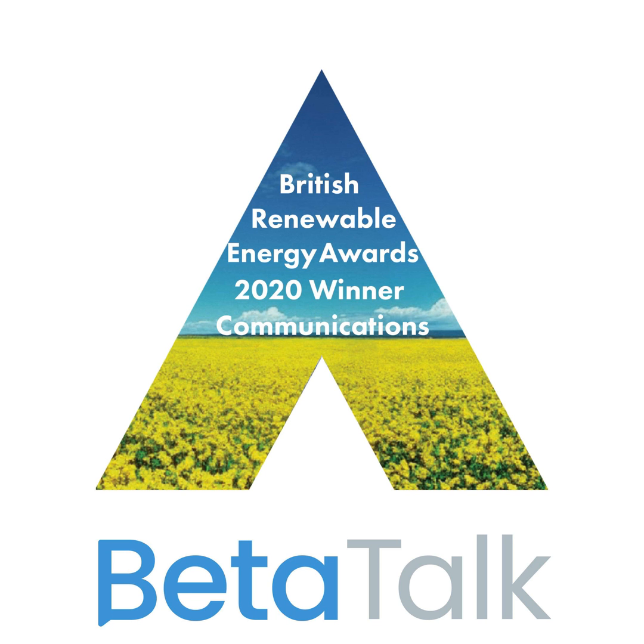Because our focus point for this was trying to make it a system that can be retrofitted into a house, or put somewhere that's hard to decarbonize. So our focus was looking at flats and apartments and other areas where you were really struggling to fit traditional air source units. And so we started from the point of, okay, what size of unit could we build, still get a reasonable heat output and a good COP from it, and then let people install that and keep it quite simple. It runs off a 13 amp plug, all the stuff that, when you get into installing a heat pump, you need to consider.